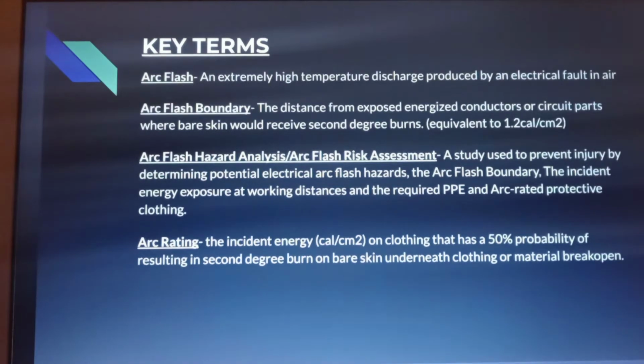And then we have arc flash hazard analysis and arc flash risk assessment. So the analysis is a study used to prevent injury by determining potential electrical arc flash hazards. The risk assessment considers the incident energy exposed at working distances and the required PPE and arc rated protective clothing. And then arc rating is the incident energy in cal/cm² on clothing that has a 50% probability of resulting in a second-degree burn on bare skin underneath clothing, or material break open.